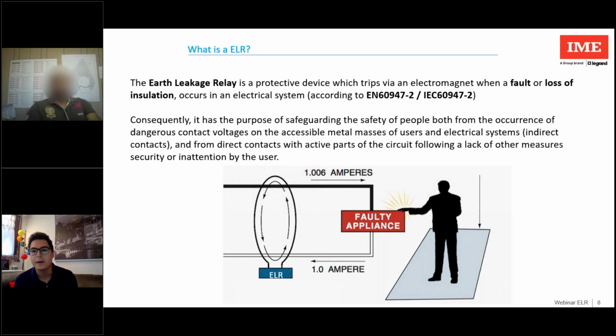The ELR is a protective device that detects the fault or loss of insulation and acts accordingly. Generally, it is going to release the main switches, therefore removing the voltage from the circuit. Thus, the threat of danger will be eliminated, safeguarding the safety of people and the object.